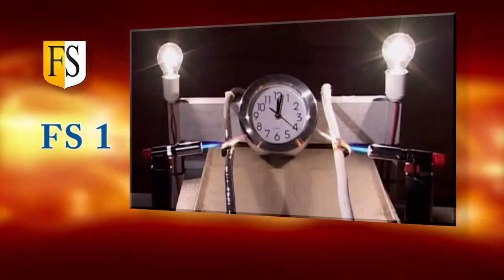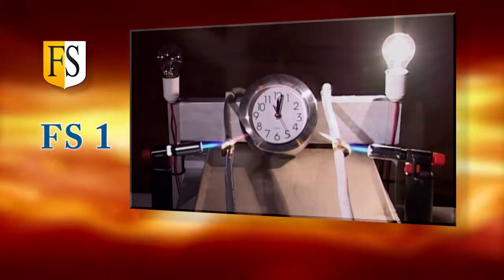Normal cables, such as flame retardant and fire resistant cables, cannot withstand such a fire, and vital cables are often routed through high-risk areas. As we can see in this test, a short circuit has occurred in the unprotected cable after less than 2 minutes.